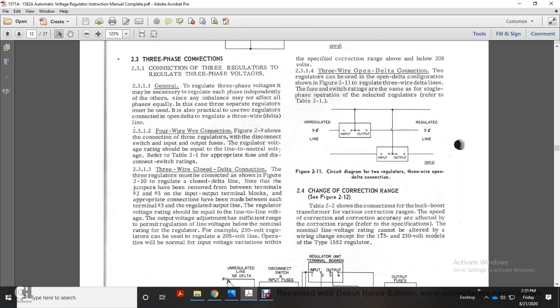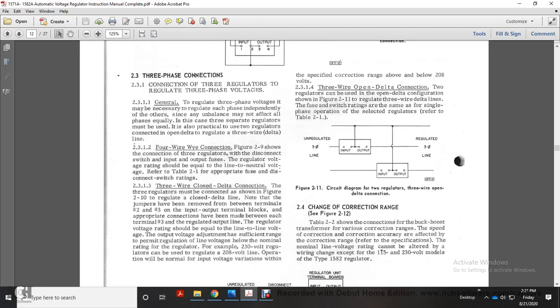2.3.1.3, 3-wire closed delta connection. The 3 regulators must be connected as shown in Figure 2.10 to regulate the closed delta line. Note that the jumpers have been removed between the terminals for the number 2 and 3 input-output terminals, and the appropriate connections have been made between each of the terminals. The regulator voltage rating may be equal to line-to-line voltage. Output voltage adjustment has sufficient range to permit regulation below the nominal rating of the regulator. For example, the 230-volt regulator can be used to regulate a 208-volt line, operating normally with input voltage variation within the specified correction range above and below the 208 volts.